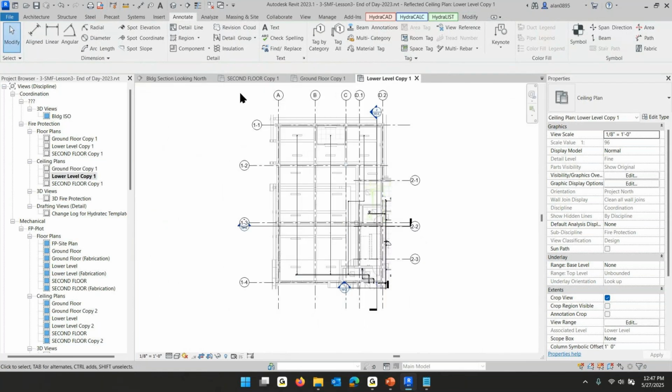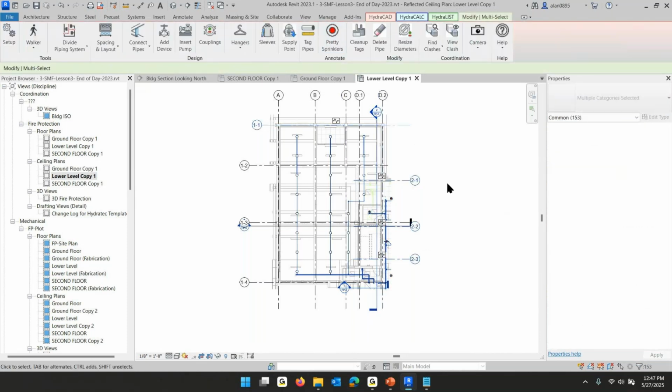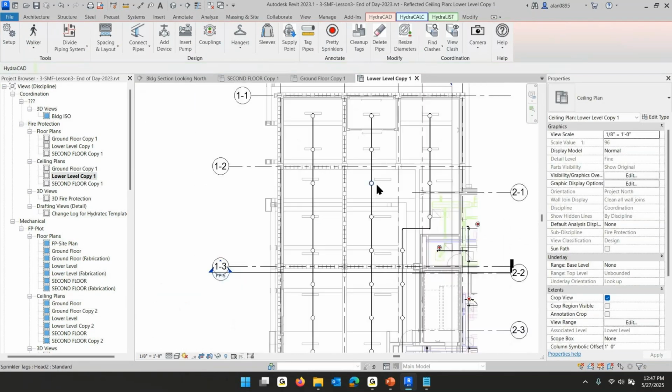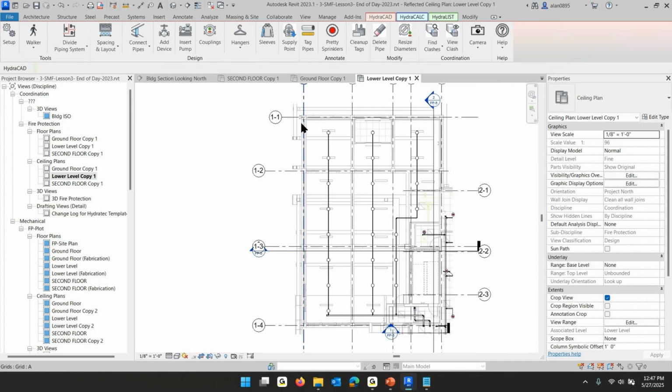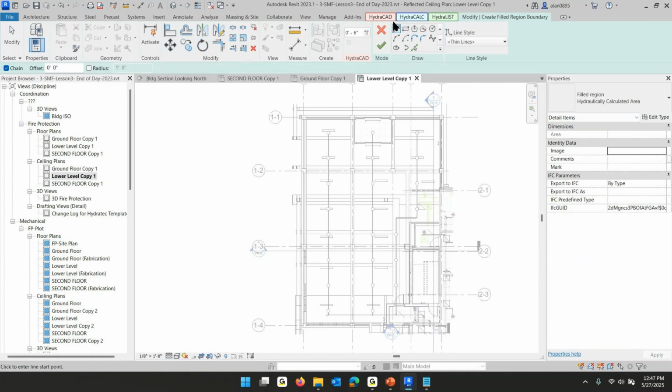This one, I can't see the sprinklers right now, so I'm going to use the pretty sprinklers button, and I'm going to use the same trick here. I'm going to start my remote area here, go at least 47 feet. So I'm going to go to annotate, region, start with a line, start in this corner, and I'm going to come down till I'm at least 47 feet. That would be halfway between those two heads.